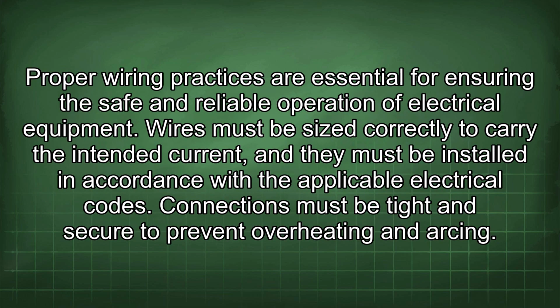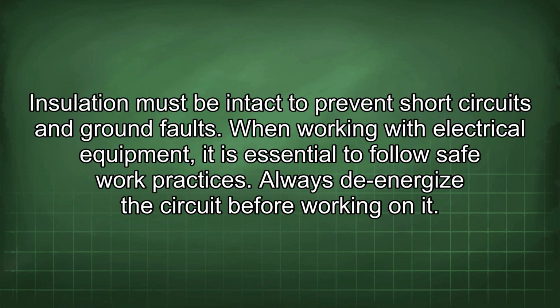Proper wiring practices are essential for ensuring the safe and reliable operation of electrical equipment. Wires must be sized correctly to carry the intended current, and they must be installed in accordance with the applicable electrical codes. Connections must be tight and secure to prevent overheating and arcing. Insulation must be intact to prevent short circuits and ground faults.